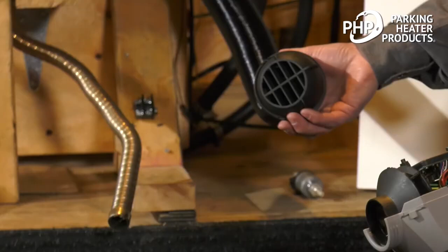We can start to feel some heat coming out of this, and a few moments later we'll see the glow pin switch off. There's a little symbol on our operating switch that monitors the system and tells us what's going on. Now the glow pin is switched off, and any new fuel coming into the heater is being ignited by the existing flame.